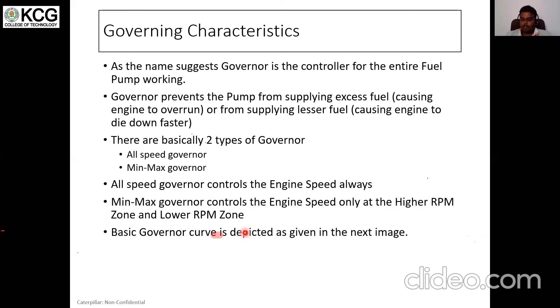So if you see here, this is a basic governor curve, again a fuel versus speed curve. As the speed increases, the fuel gradually drops and keeps dropping, and at 2420 rpm, which is 10% above the rated speed, you have your governor point set, which is your high idle speed. The engine is set at high idle, and if the speed overshoots high idle, the fuel will gradually drop down and it will dive the engine.